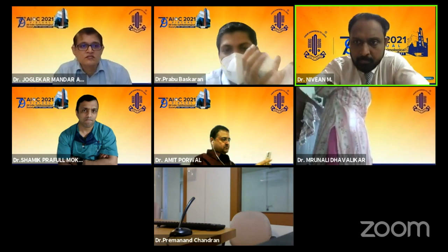So I really don't want to recommend it because of the pressure that they're putting over the cornea. We're still working on how, when we reduce the distance, either the needle has to be designed slightly differently or the haptic has to, you need to do something. We are still working on it. So that's why, for the current version, we recommend the larger section.